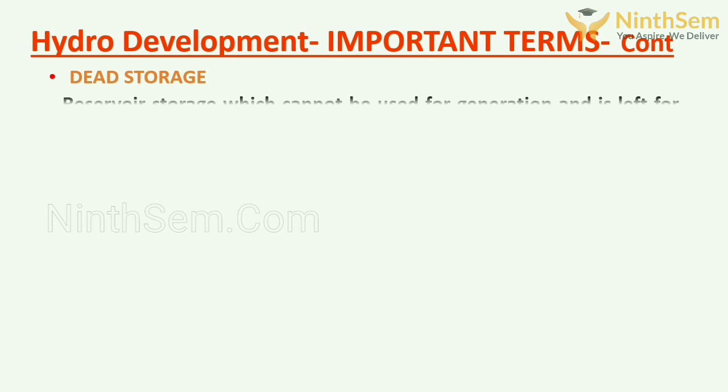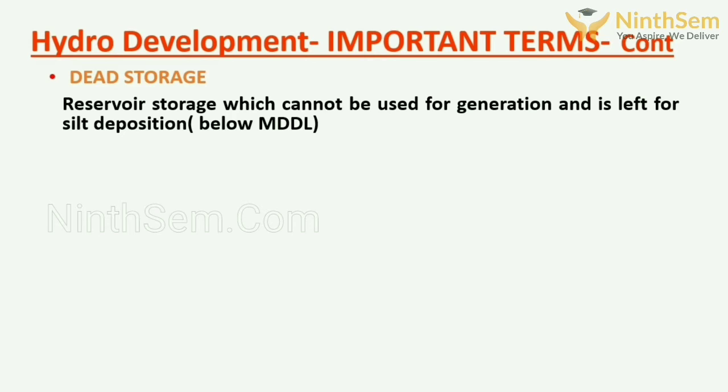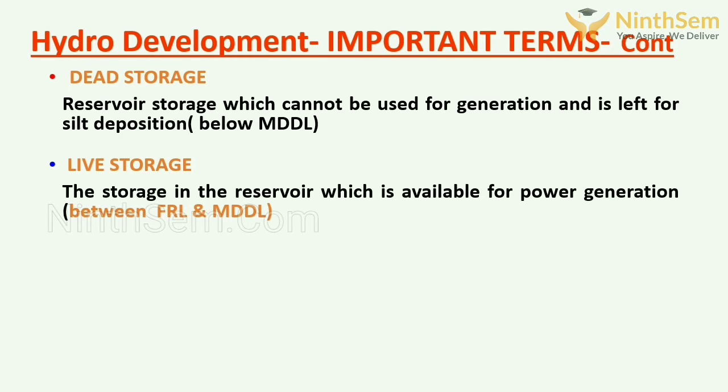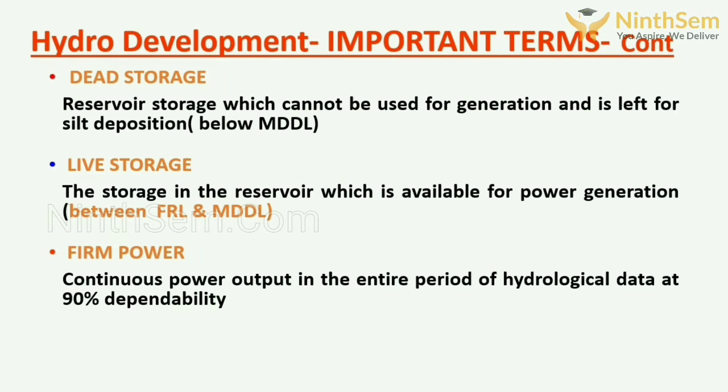Hydro development important terms as follows: dead storage, reservoir storage which cannot be used either for generation or is left for silt deposition. Live storage, the storage in the reservoir which is available for power generation. Firm power is the continuous power output in the entire period at 90% dependability.